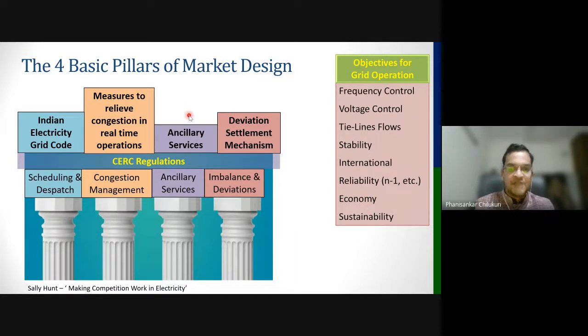That means we might increase generation in area 2 in such a way that congestion is alleviated in real time. Suppose even though we have scheduled power between area 1 and area 2 as 80 megawatt, in real time the power flow is 90 megawatt because area 2 is drawing a lot of power. Then we increase generation in area 2 by 10 megawatt by deploying ancillary services, so that the flows are minimized and frequency is restored.